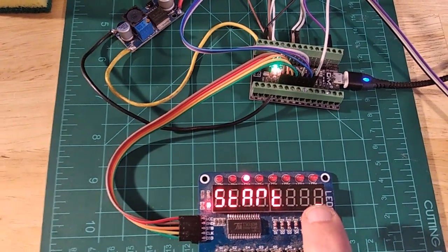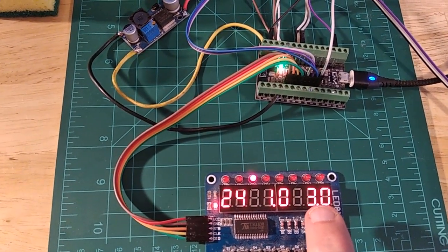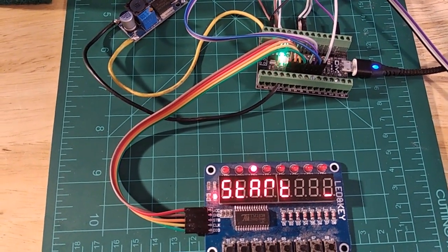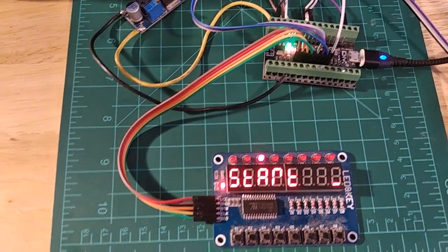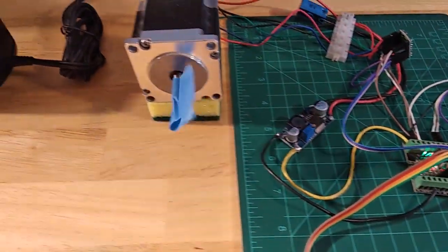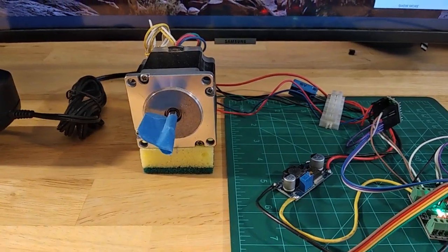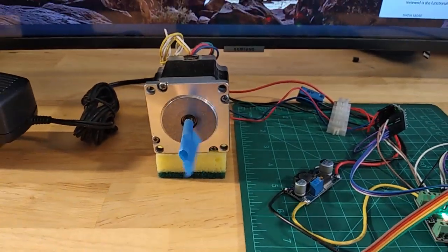Here you have the pressure that will be used to limit the motor movement, to avoid having too much high pressure on the air that's delivered to the patient. So let's start it. So it does this movement.